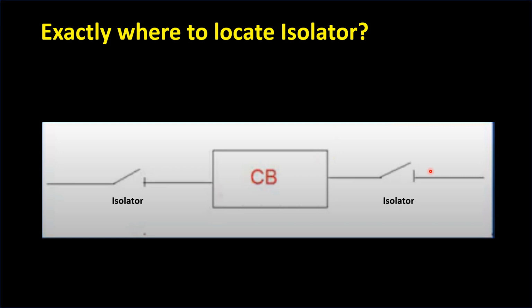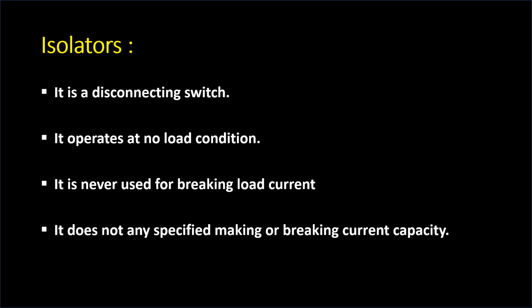Now let's switch on to our main point. What is isolator? Isolator is a disconnecting switch. It is somewhat different than a normal, ordinary switch. It is only and only used for disconnecting purpose or isolation purpose. It operates at no load condition. Please remember this point. Isolator always operates at no load condition.